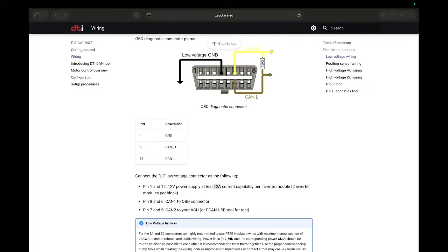Also keep in mind that with the position sensor attached, the power draw will be more than just the standalone inverter by itself. So what you will see on the laboratory power supply during operation is that if you attach the sensor, especially if it's a resolver, because it takes a little bit more than a conventional encoder, it will consume more, and that's fully normal for the operation.